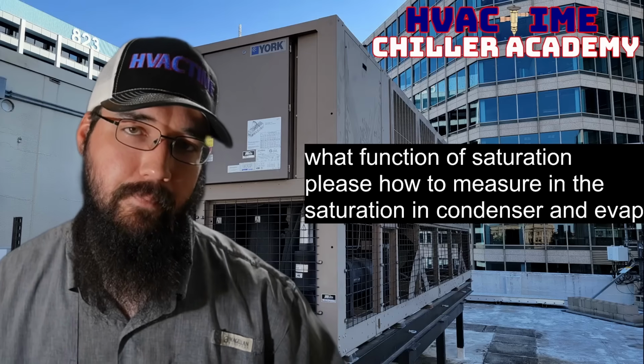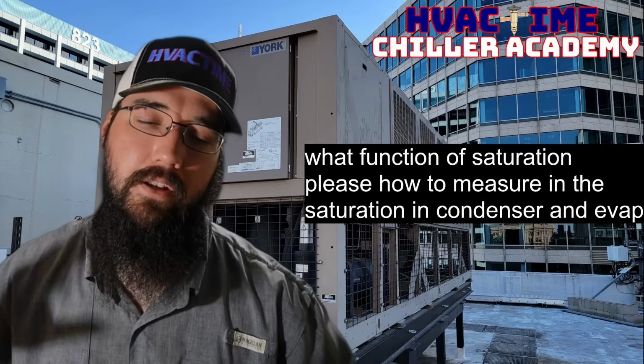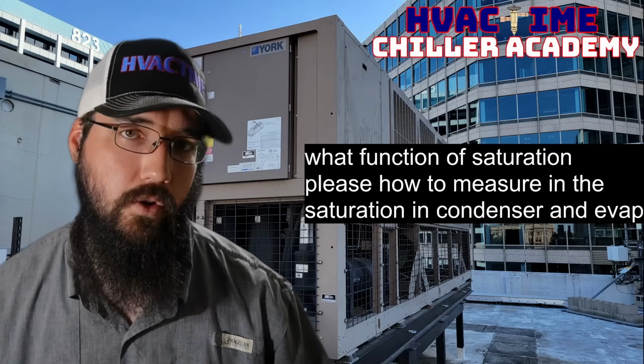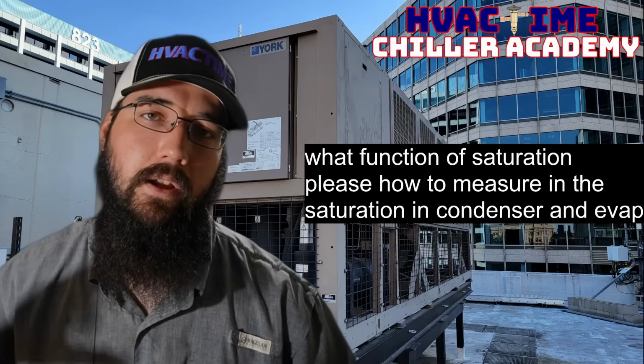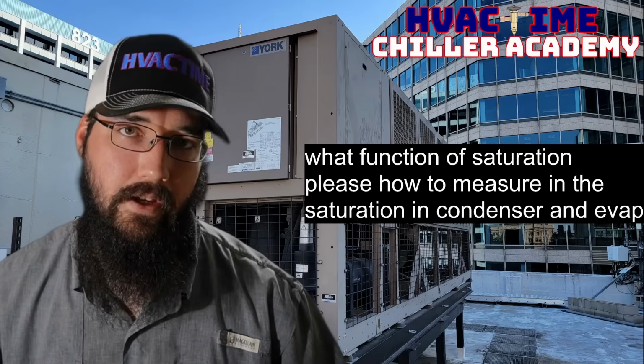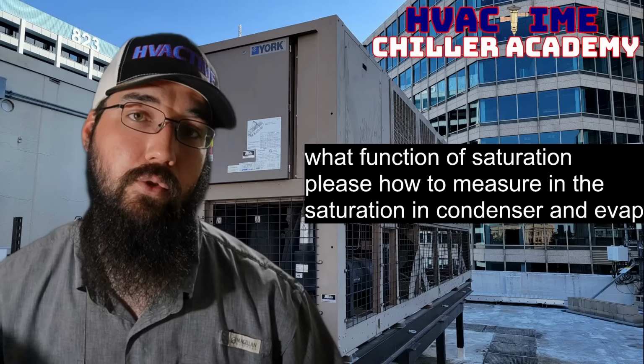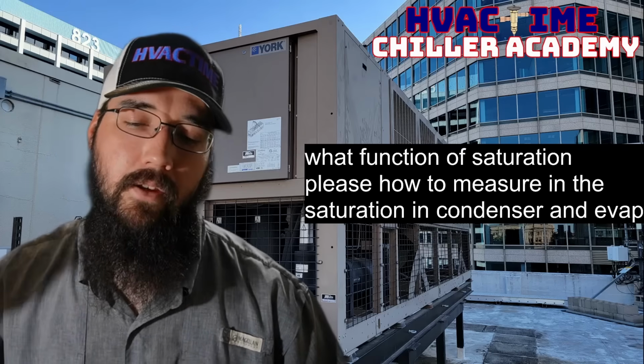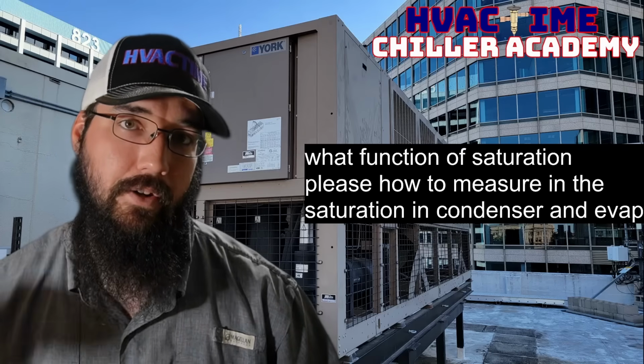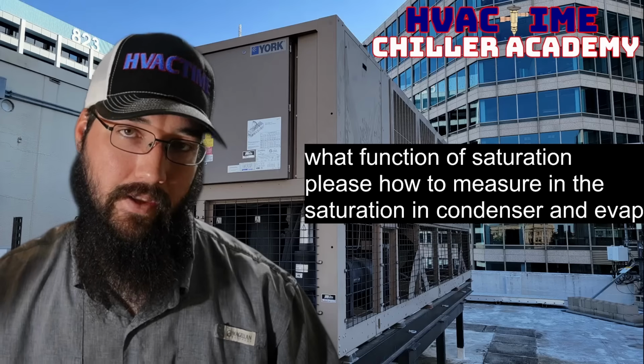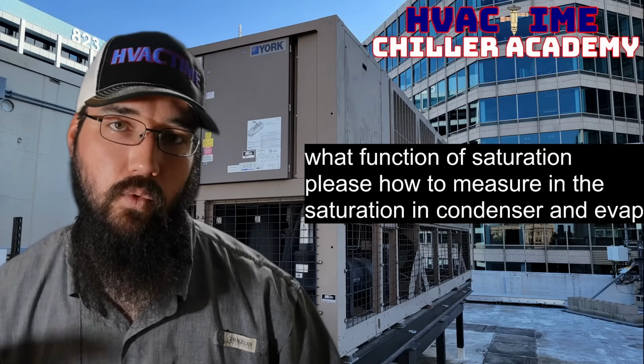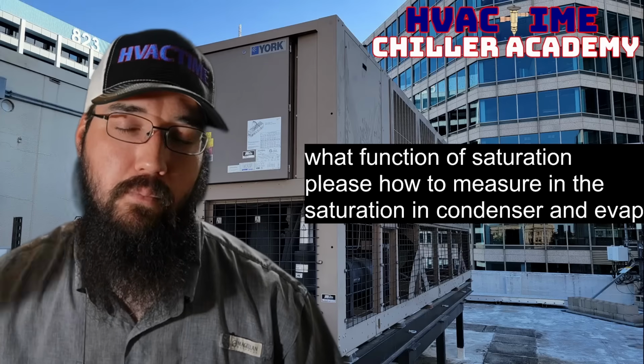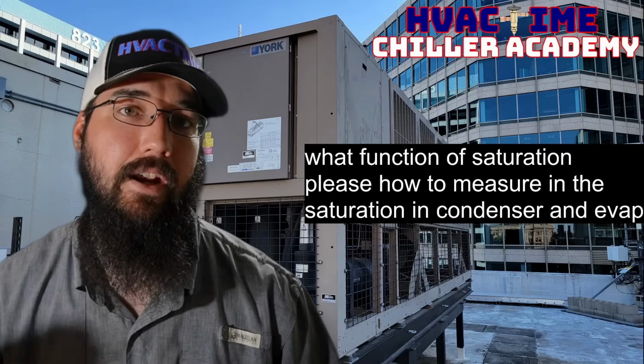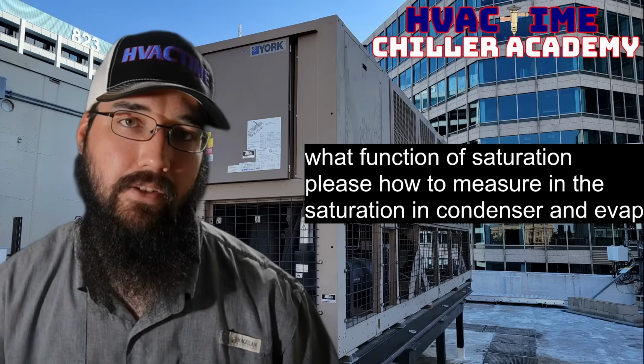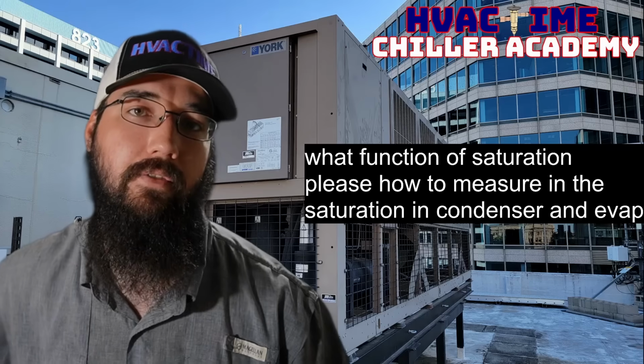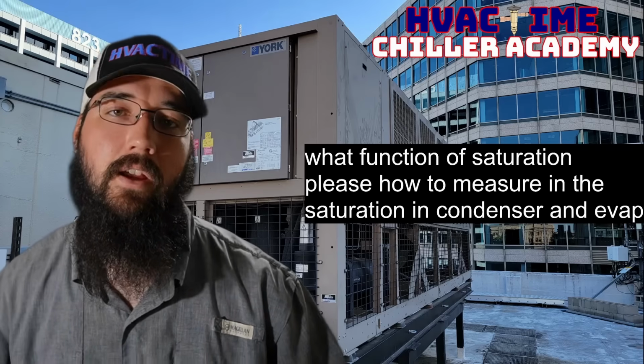So in the evaporator, we need that saturation temperature you'll see on the PT chart to be lower than the water temperature. And then on the condenser side, let's say it's a water-cooled condenser, for example, we want to reject heat that way. We want to get rid of it into the water in the condenser. So that saturation now needs to be so much higher than the condenser water temperature so that we can move enough heat at a high enough volume to get that into the water to then be carried off and gotten rid of somewhere else.